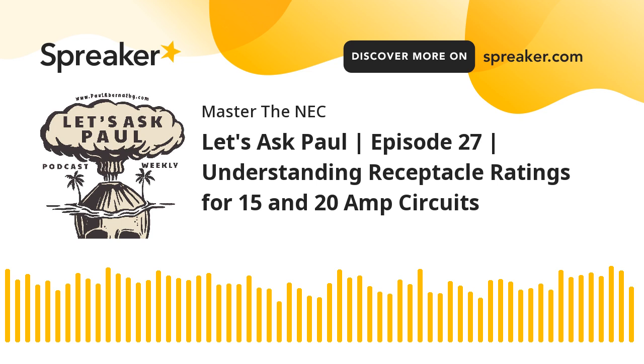So you're going to see throughout the code where it makes references, and you're going to notice that in 210.21 B1, 2, and 3 that we're going to be talking about, most notably B1 and B3, it talks about the receptacles, and it'll either be a single receptacle or 2 or more, which is a duplex, okay? But it could be a quadplex, could be a triplex, okay? But it is definitely 2 or more, and that is what you're going to deal with. So simplex, single; duplex, 2 receptacles. Okay, keep that in your mind.